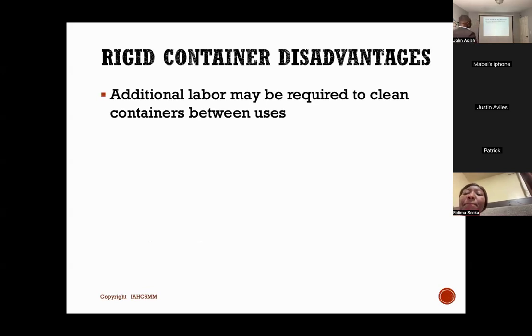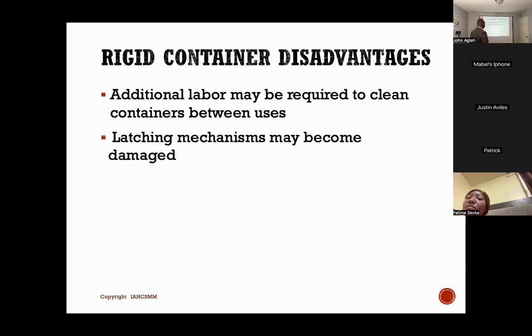Additional labor may be required to clean containers between uses. When rigid containers come to decontamination, remember, blue wrap will be thrown out in the trash bin up in the OR, but the rigid container will come down to us with the instrumentation, and then we will have to reprocess the instrumentation as well as the containers. You see how that works? So when we're talking about additional labor required, that is it. You clean the containers, and then you clean the instruments as well.